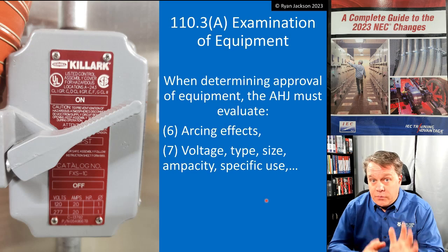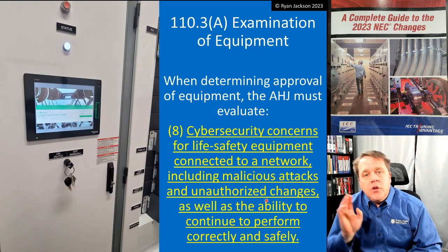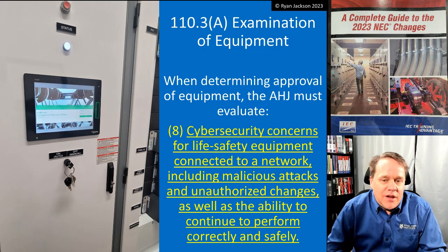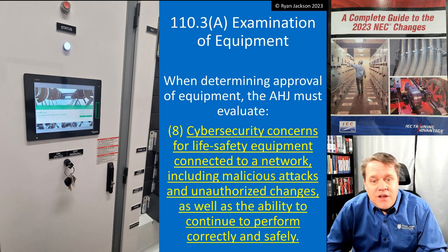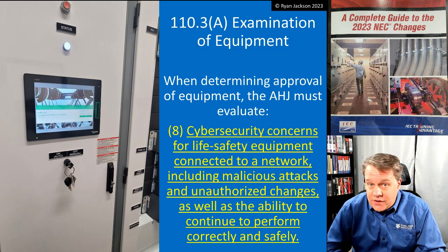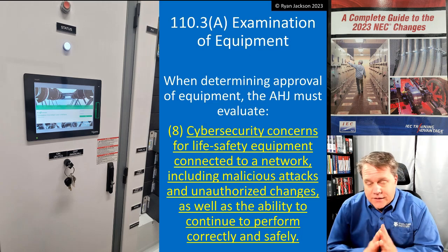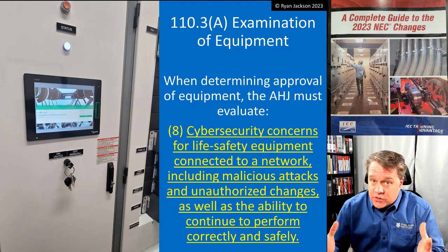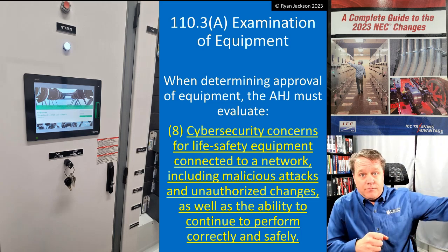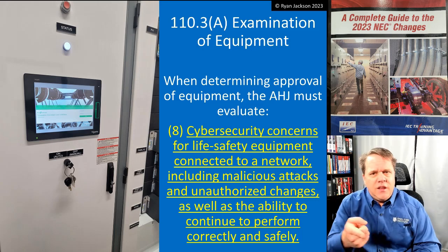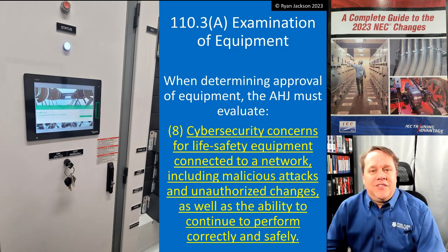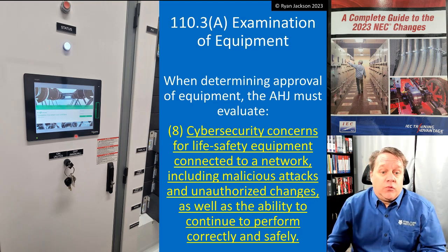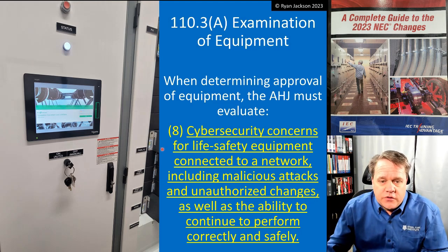New to this version of the code, Item 8 was added: cybersecurity concerns for life safety equipment connected to a network, including malicious attacks and unauthorized changes, as well as the ability to continue to perform correctly and safely. New switchgear and switchboards — modern equipment — does not look anything like what we installed 30 years ago. These days you can get switchgear and switchboards with a full-blown computer on them. What we're looking at here is a switchboard with a computer on it.